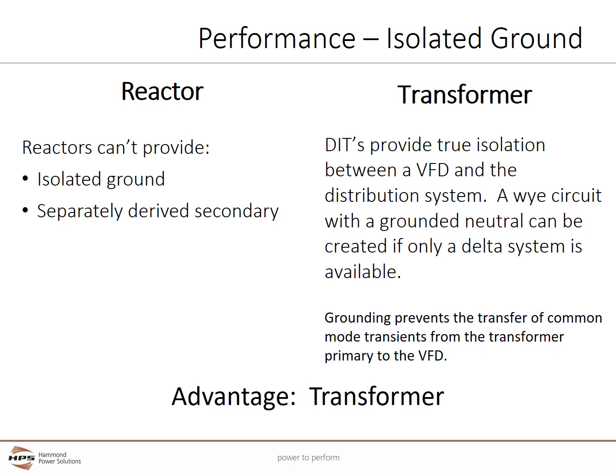DITs provide true isolation between a VFD and the distribution system. A Y circuit with a grounded neutral can be created by a DIT secondary if only a delta system is available. Grounding the secondary Y neutral circuit also prevents common mode transients from the transformer's primary from reaching the VFD. As a result, transformers are preferred to provide a true isolated ground for a VFD.